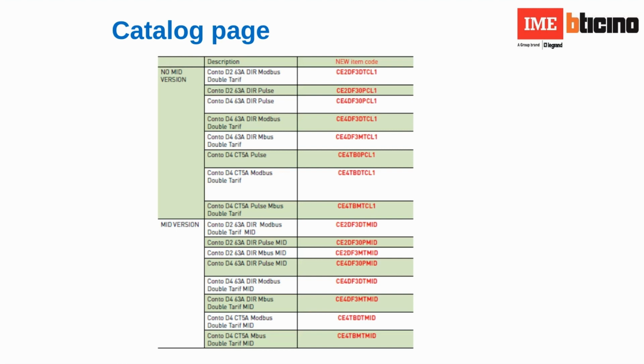So this is the catalog page. As you can see, we have MID and non-MID certified energy meters. We have, as I said, single phase, 3 phase, direct and indirect, and with external communication in Modbus or MBus, which is another communication protocol, or just a pulse output.